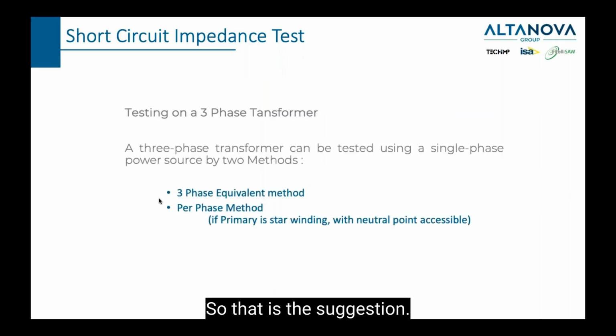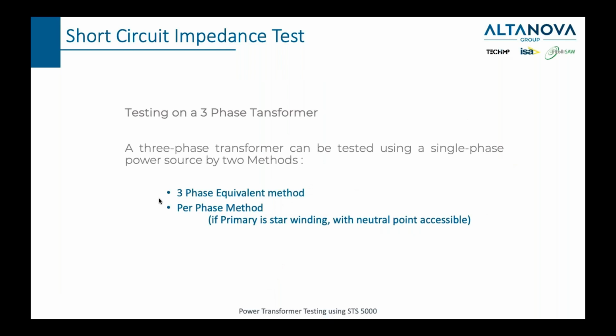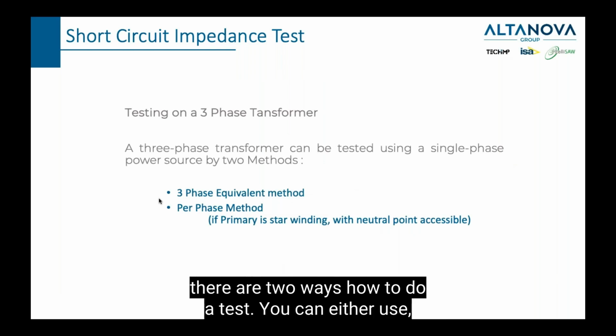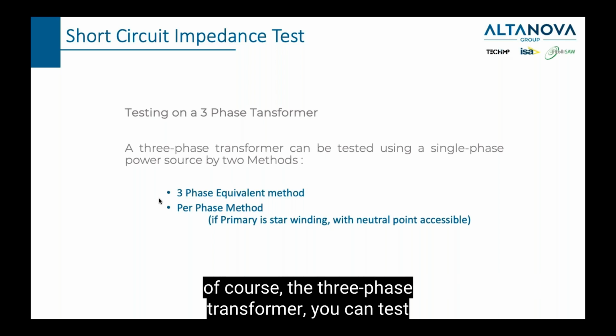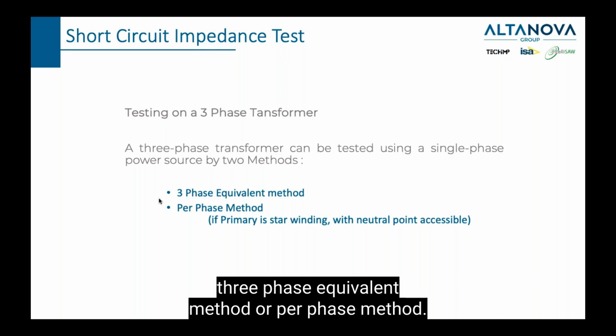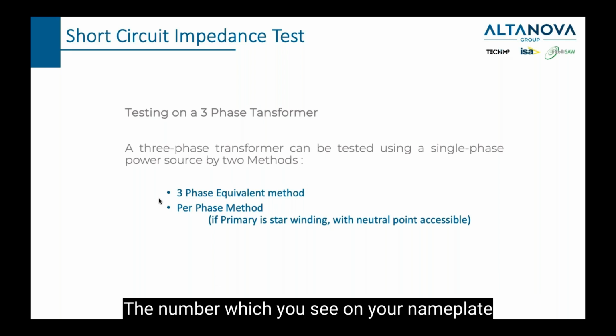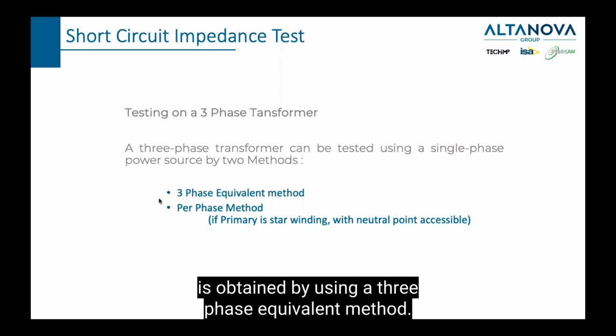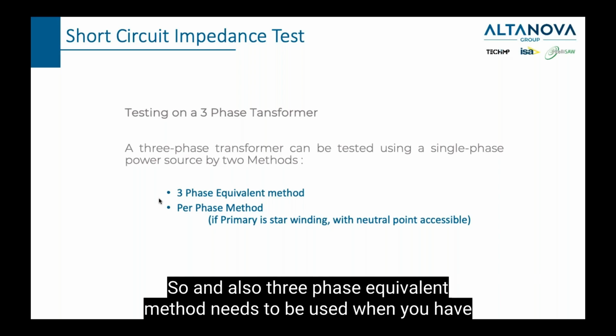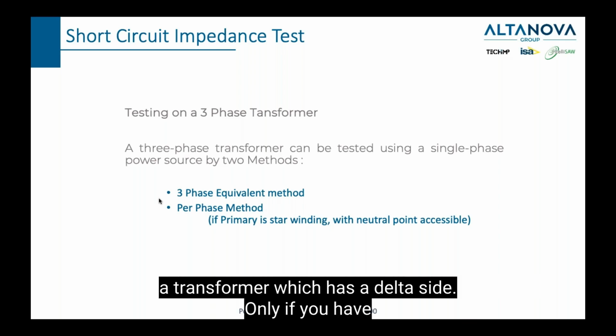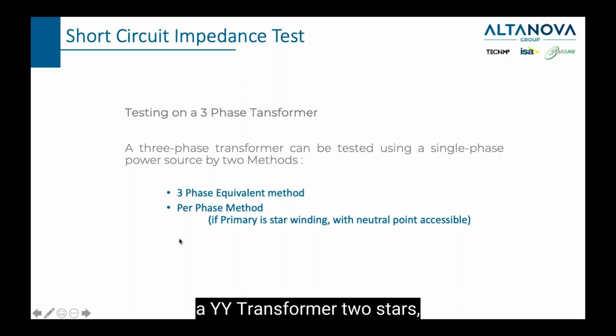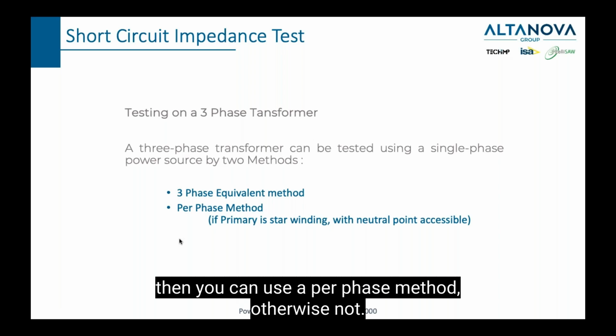So that's the suggestion. When we are actually doing a test, there are two ways to do it. When you're testing a three-phase transformer, you can use the three-phase equivalent method or the per phase method. The number which you see on your nameplate is obtained by using the three-phase equivalent method. Also, the three-phase equivalent method needs to be used when you have a transformer which has a delta side. Only if you have a YY transformer, two stars, can you use the per phase method, otherwise not.